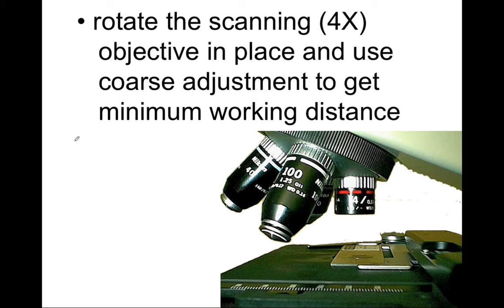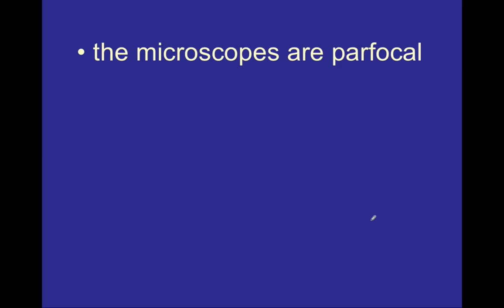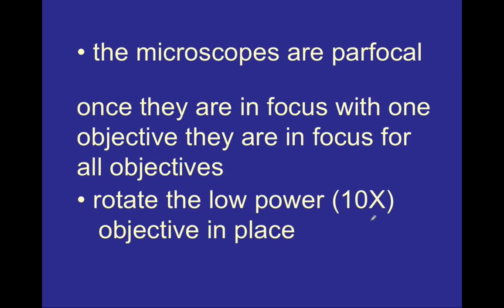As you look through the ocular lens, use the coarse adjustment knob to bring the stage up closer to the scanning objective until that picture is finally in focus. At this point you are looking for the minimum working distance that gives you a nice clear picture. You can use the stage adjustment knobs to move the microscope slide around, but always start with the coarse adjustment knob, and only after that will you use the fine adjustment knob to make very minor changes in the working distance.